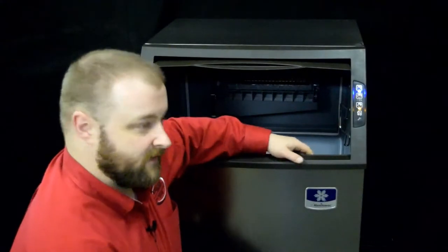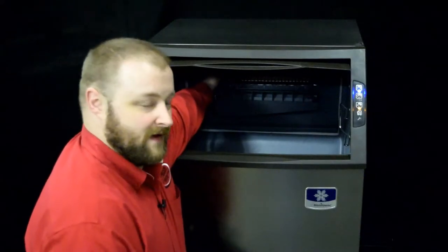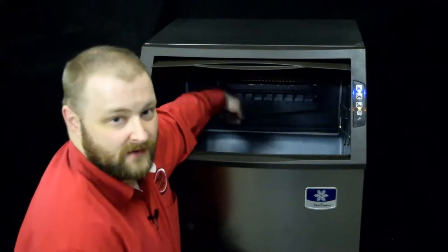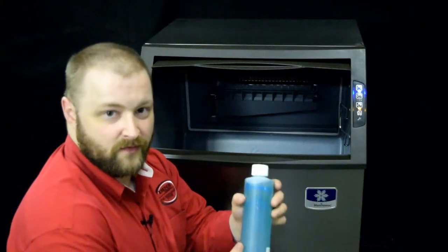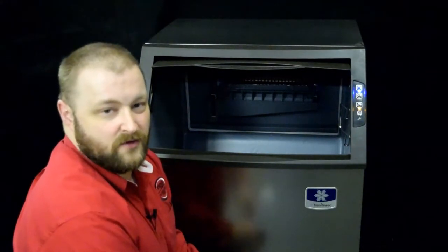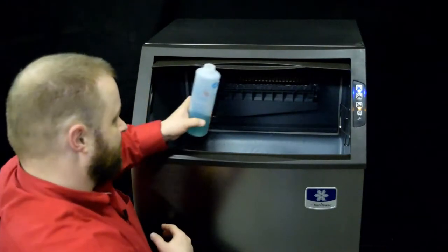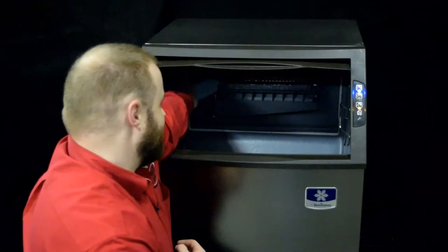Once the cleaning process begins, the water trough will begin to fill with water and then water will begin to cascade over the evaporator. This is when we'll introduce our Manitowoc cleaning solution. Now I'll pour the solution into the water trough. I'm going to use about two ounces. I'm going to pour it right here.